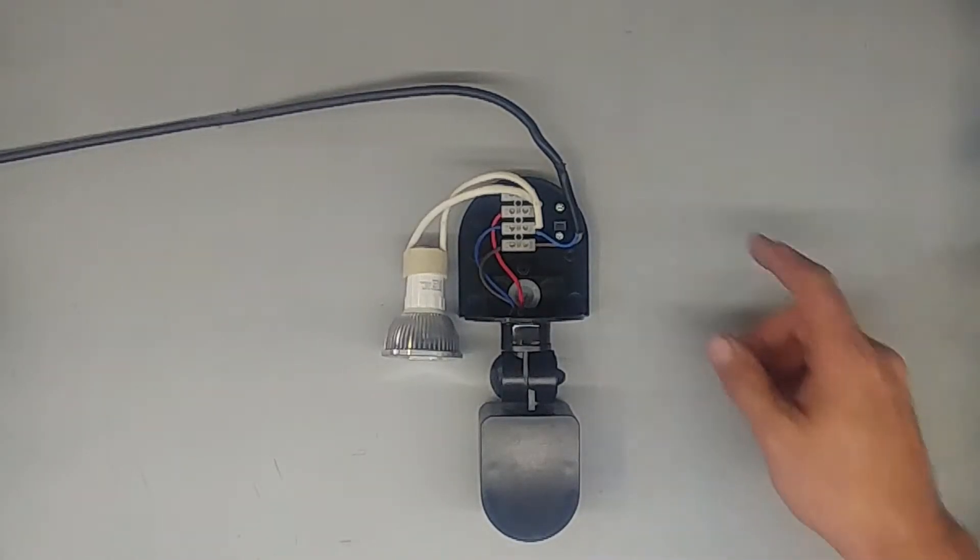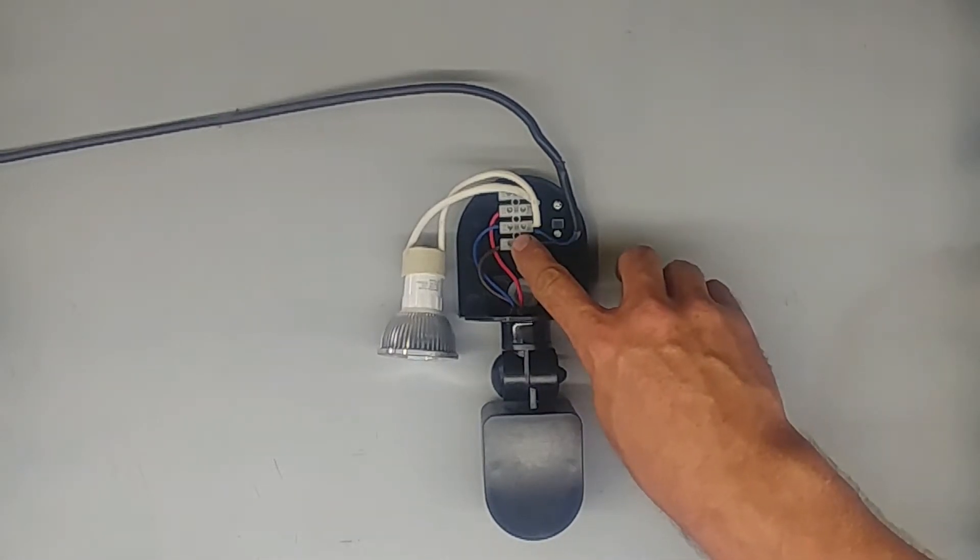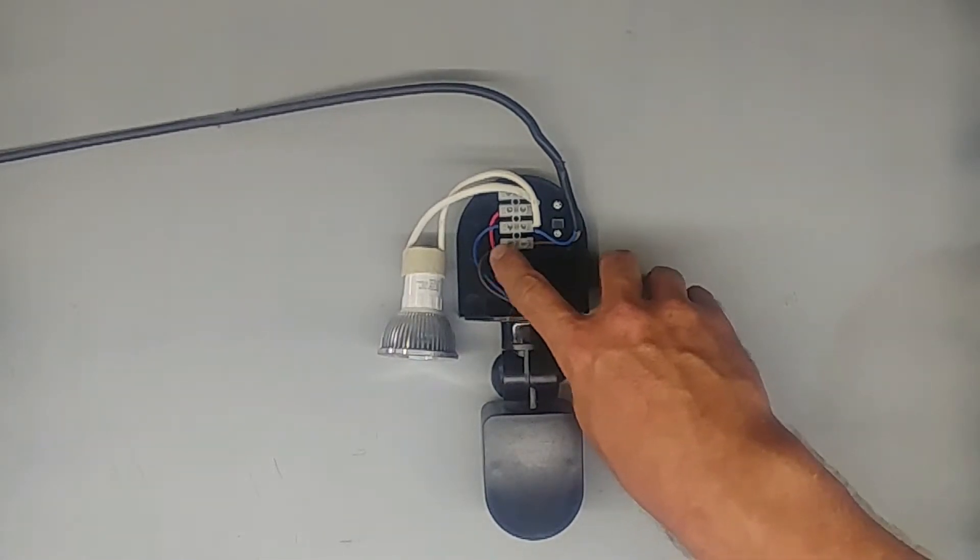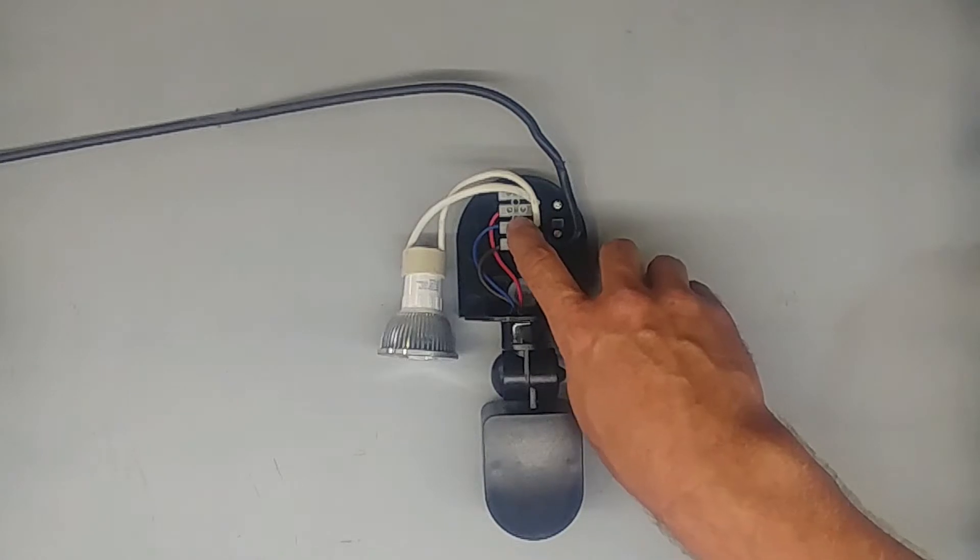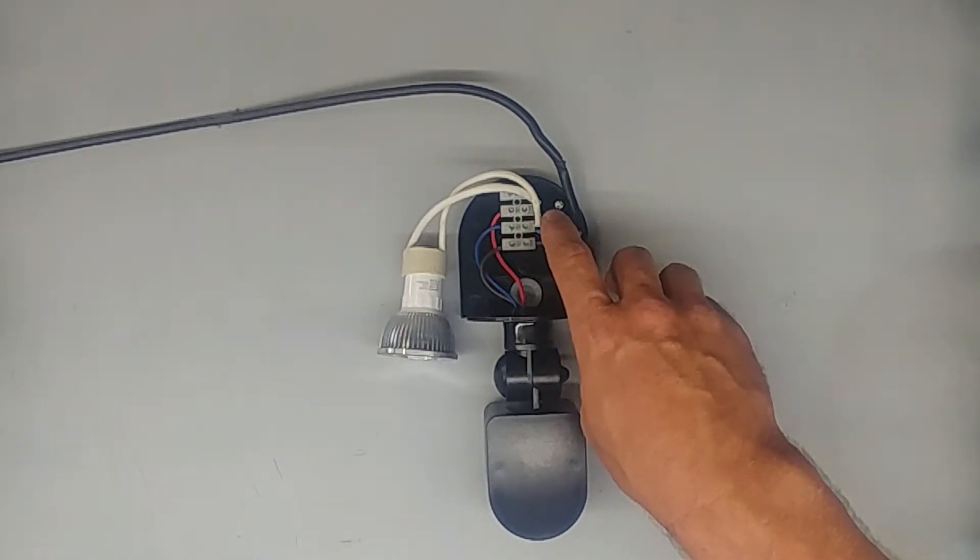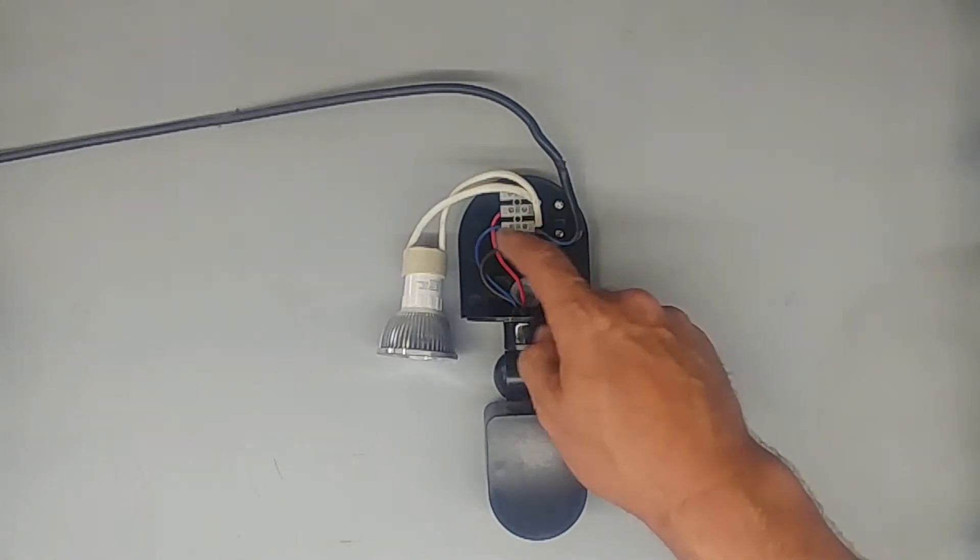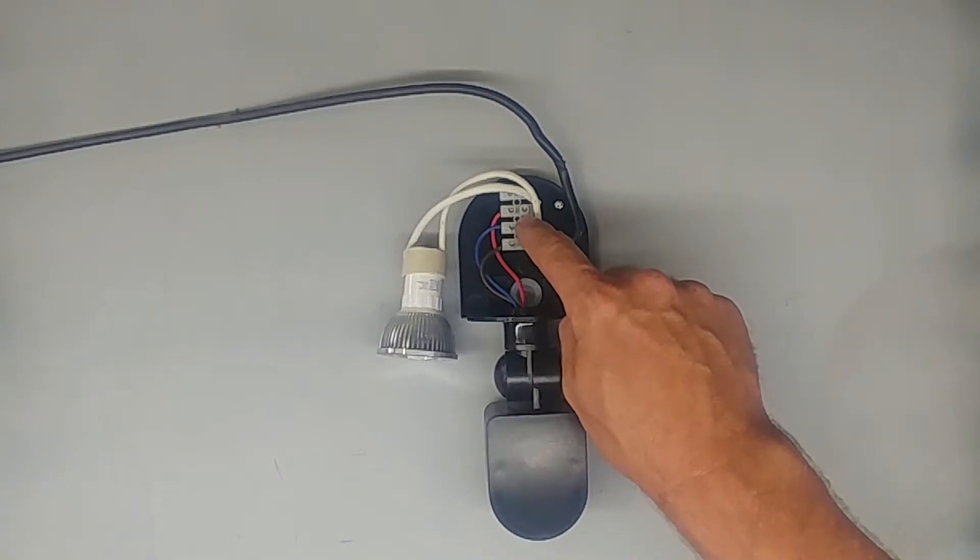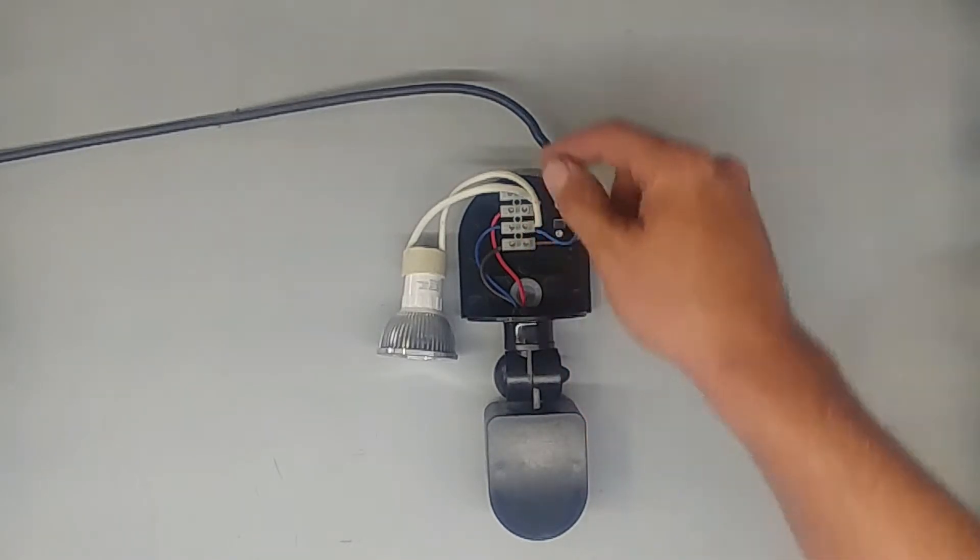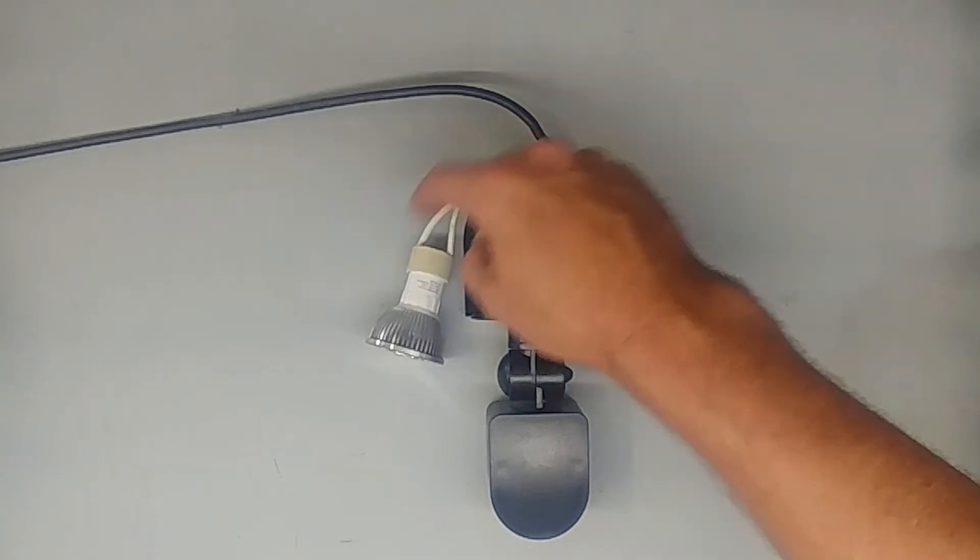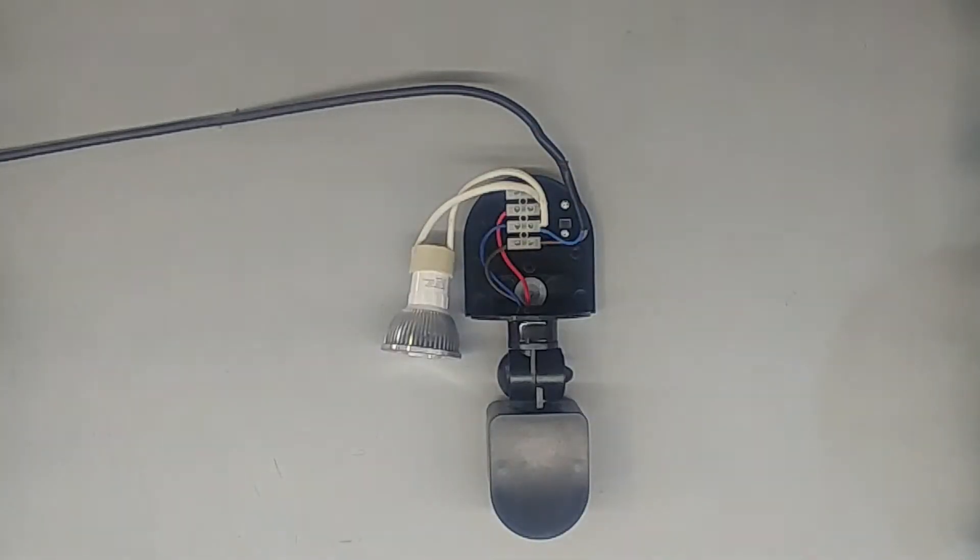You can see what I did here is just connect the live wire to the live, so the brown wire and the brown wire, and then the neutral wire. And then also what I did was I just bridged the neutral to the light as well to the same neutral connection. And then I just put the return wire on the red one to the light. Let's switch it on and see if it works.